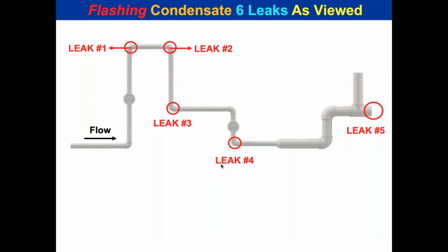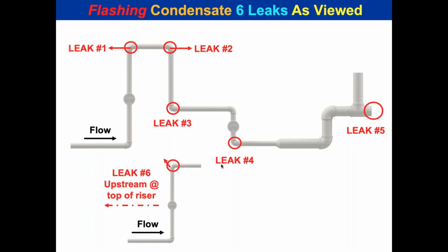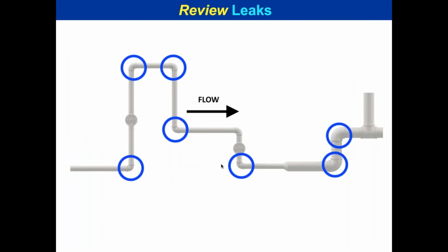So this refinery site that we talked about, they had 6 leaks. If you look there, there's 5. That's because they had another leak 6 to the left of the line. That's where the leaks were. So here they got back slams because the pocket was reversing. The pocket would collapse right here, and then you would send a force vector back. So they were getting a blowout there.